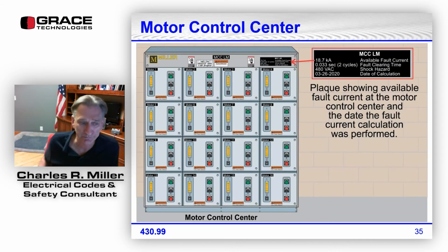So a Motor Control Center, it is required, again, on a plaque in the upper right corner showing the available fault current, showing the fault clearing time, showing the voltage, and showing the date of the calculation. Of course, right in the center upper part is an arc flash warning label in accordance with NFPA 70E. This plaque, of course, shows all the information required by Article 110 and also 430.99.